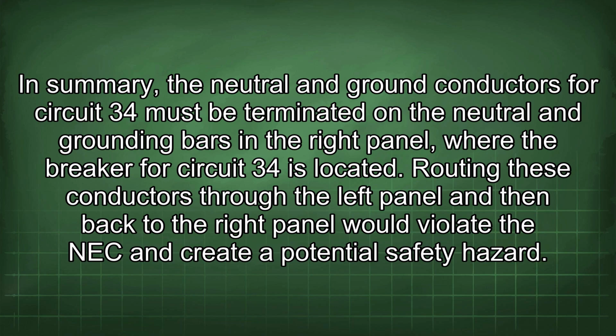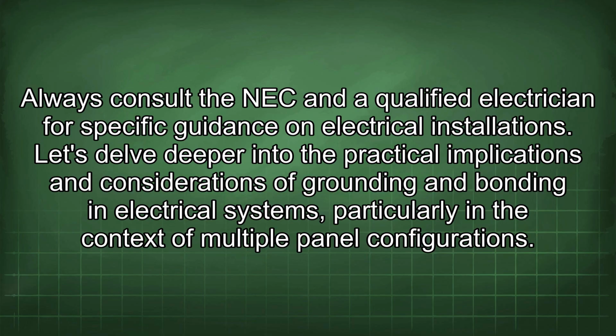In summary, the neutral and ground conductors for circuit 34 must be terminated on the neutral and grounding bars in the right panel, where the breaker for circuit 34 is located. Routing these conductors through the left panel and then back to the right panel would violate the NEC and create a potential safety hazard. Always consult the NEC and a qualified electrician for specific guidance on electrical installations.